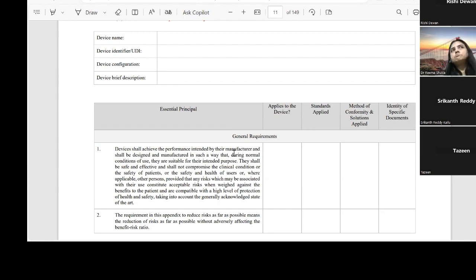No, not really. It's not similar to EU MDR because it is all as per this guideline that we have to provide. Saudi has got its own EP checklist, which is similar to the GSPR checklist of the EU, but there are certain requirements which are slightly different. There are 3 to 4 clauses which are different from the GSPR checklist. So it is not exactly as EU MDR, but more or less most of the documentation is required as per what we do for EU MDR.